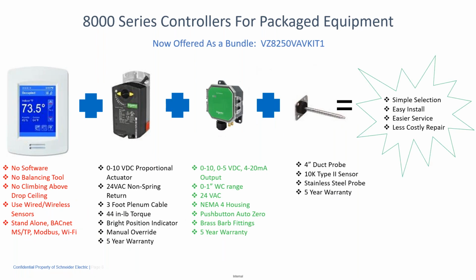We've also recently released a bundle, a kit, to make it a little bit easier. So it comes with the controller, the actuator, the pressure transducer, and the temperature sensor, right? And again, no software is required, no balancing tools are required. You get the actuator that fits the 0 to 10 volt or 2 to 10 volt output to that actuator, the pressure transducer that's a 0 to 1 inch range that fits with the controller itself, and then a 4-inch duct probe for supply air temperature sensing.